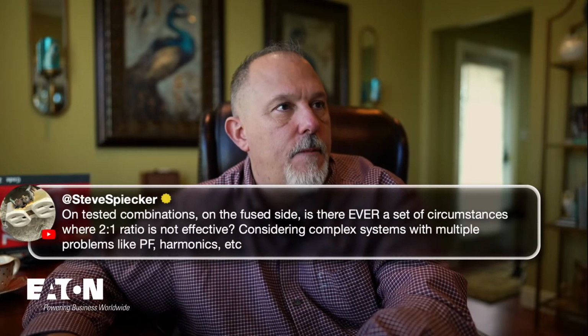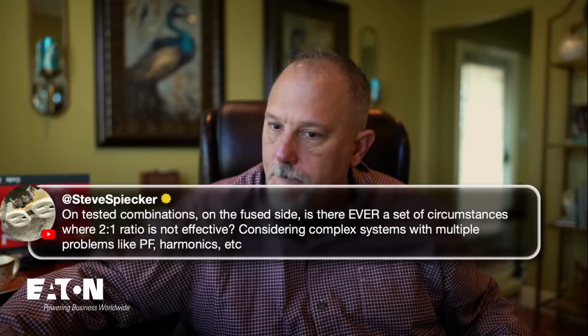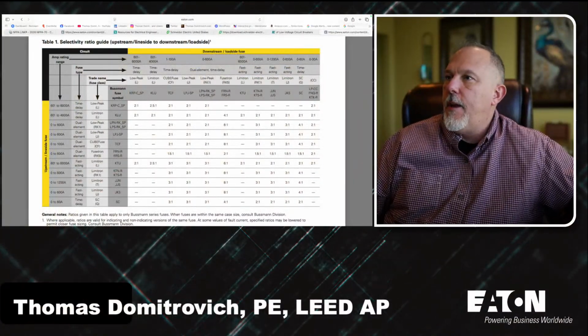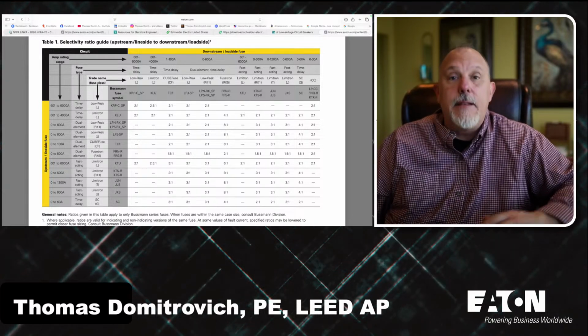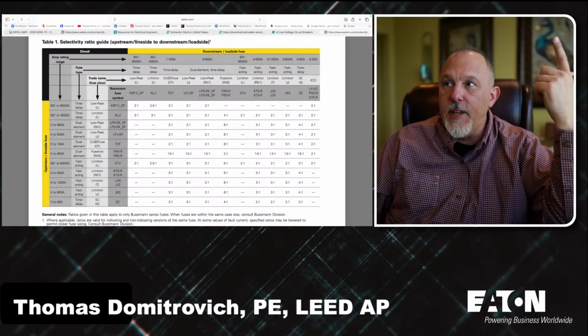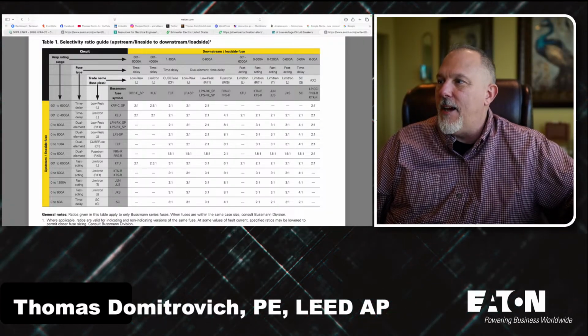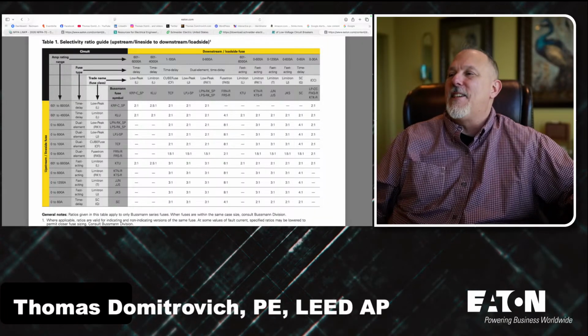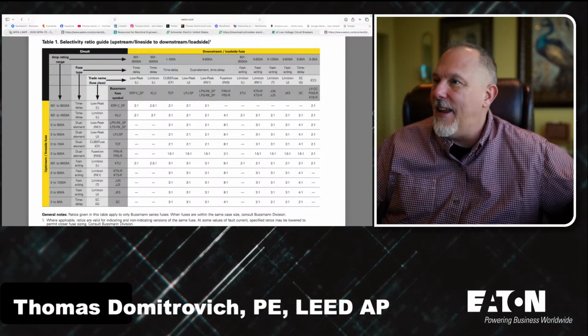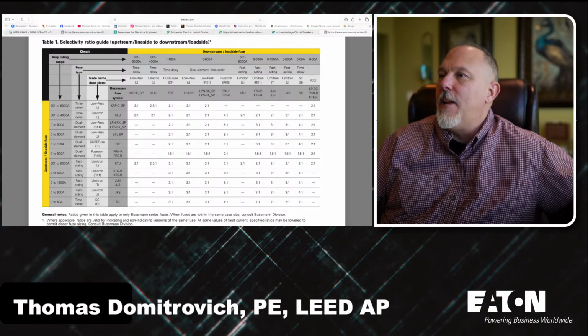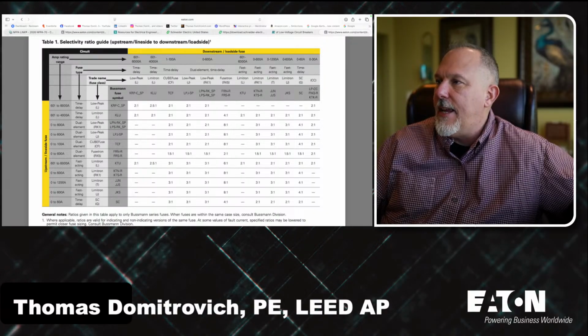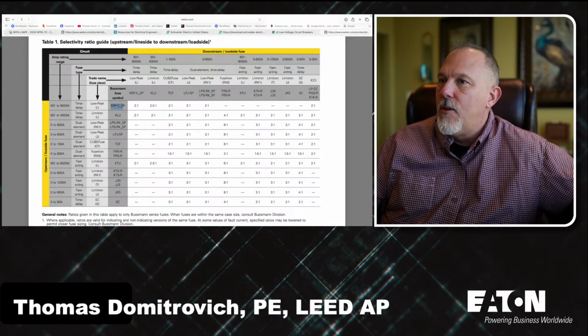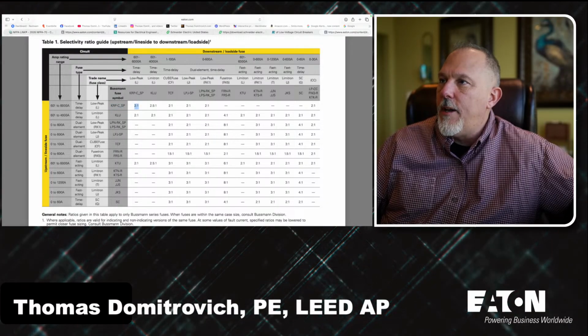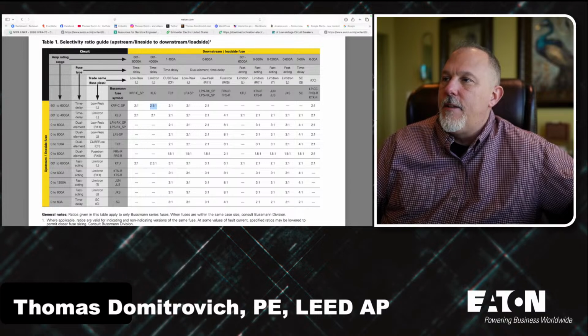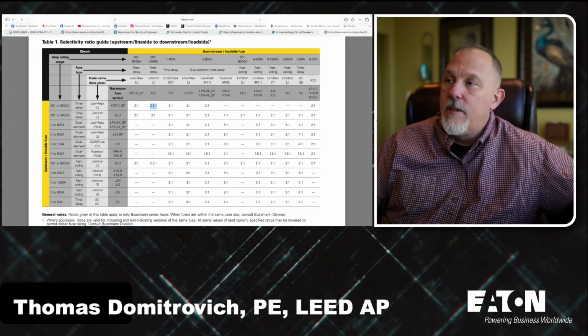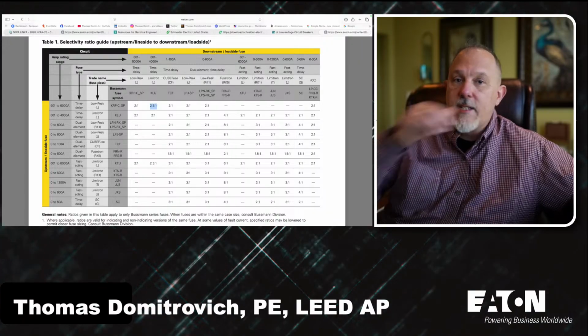This table will tell you the story. Now, I love that the Bussmann guys did it backwards. They put the downstream up top, and they put the upstream down the bottom on the left. I tried to get them to change that, and it was not going to happen. So anyway, we have the upstream device, say it is a KRP, whatever. Here's a 2-to-1, and then there's a 2.5-to-1. So I have to do 2.5-to-1, which means I'll put a little bit larger.